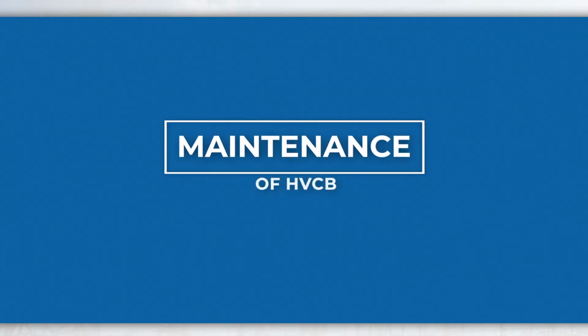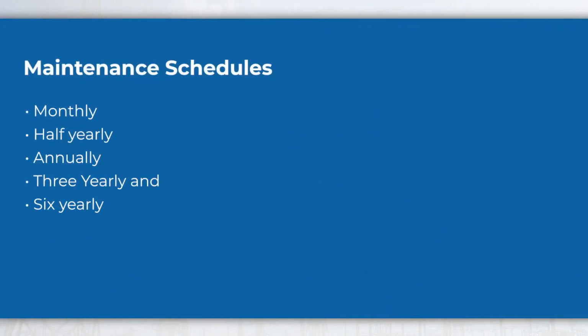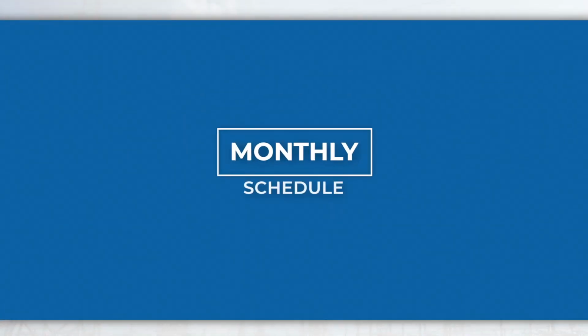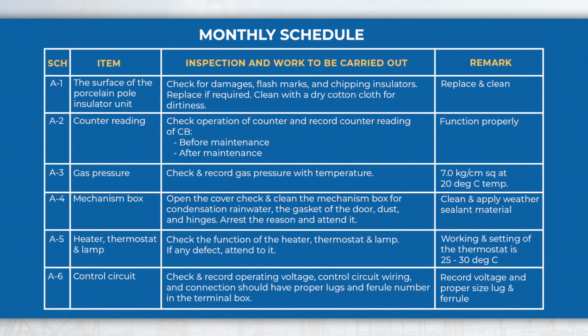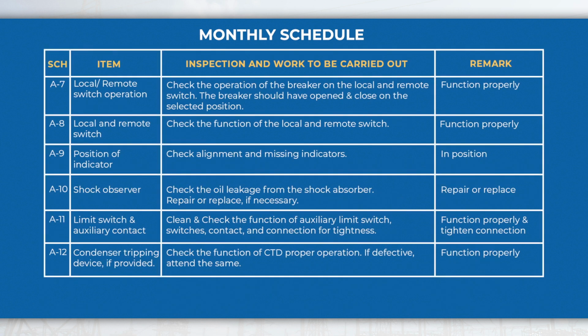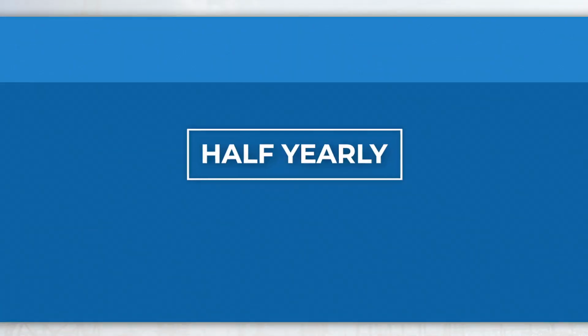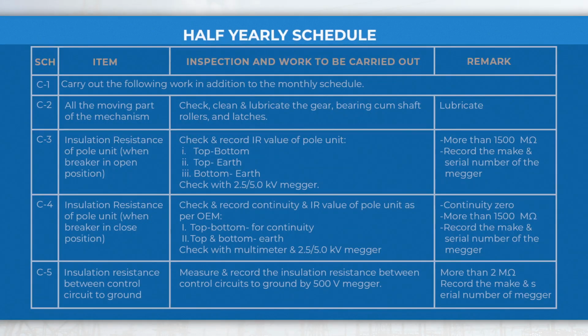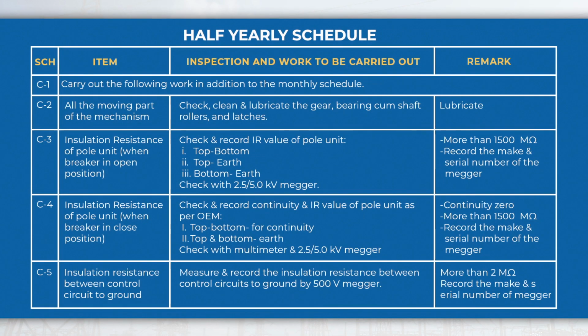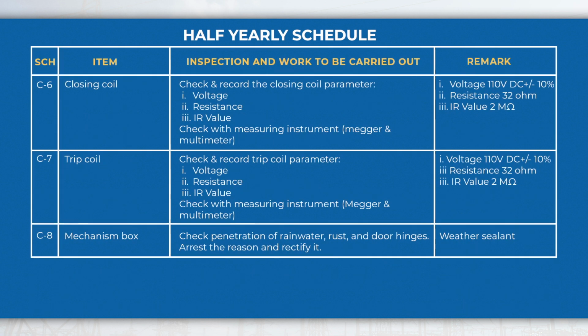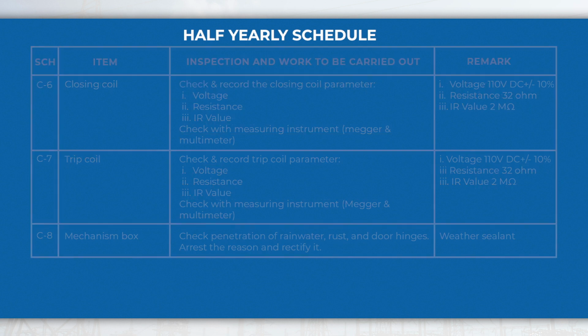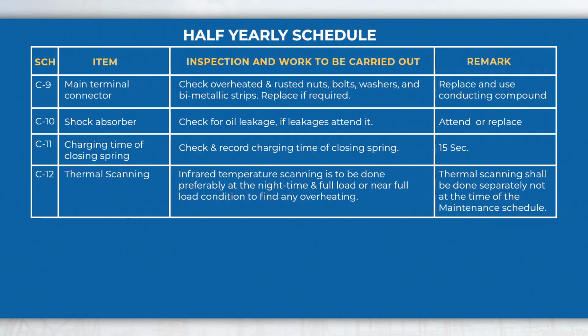Maintenance of HVCB. The maintenance of HVCB is carried out in different periods with different schedules, like monthly schedule. In the monthly schedule, perform the activities like checking the insulators, gas pressure, mechanism box, remote and local switch, auxiliary contacts, anti-pumping device, interlock, etc. Half-yearly schedule. In the half-yearly schedule, perform the activities like checking the moving parts, measure the IR value of the pole, checking of main terminal connectors, recording of charging time of the breaker, etc. in addition to monthly schedule activities.